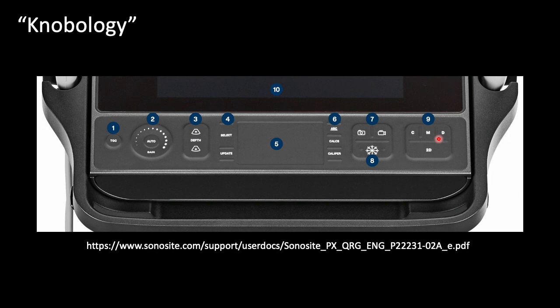On the GE Venue Go, you have a separate button or touchscreen for pulsed wave Doppler and continuous wave Doppler. Whereas on the Sonosite, you have a single D for Doppler. Then you would have to come to your touchscreen up here to choose your option of, do I want pulsed wave or do I want continuous wave Doppler? It just depends on the machine.